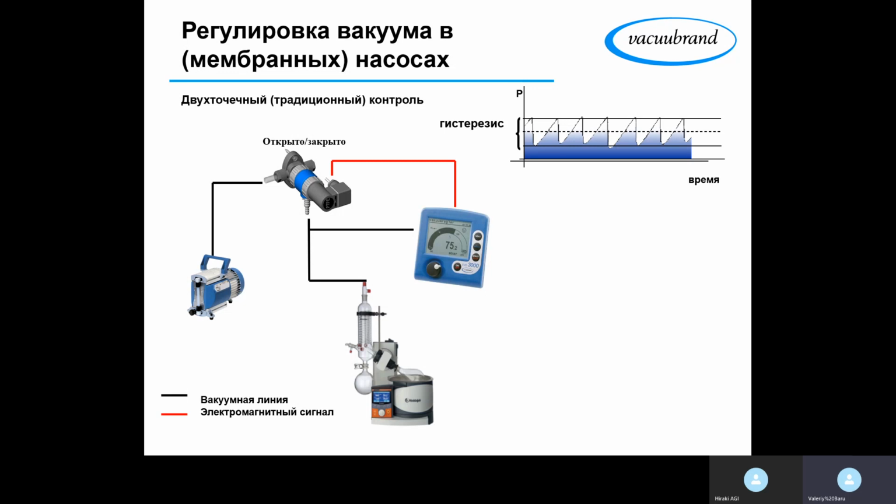Most customers, like with the vacuum which we discussed already, are not thinking about the performance at a certain vacuum, but they are thinking about the vacuum level. And I explained to you why we need to choose the pump that will have a certain performance at the vacuum level that we are going to operate at.